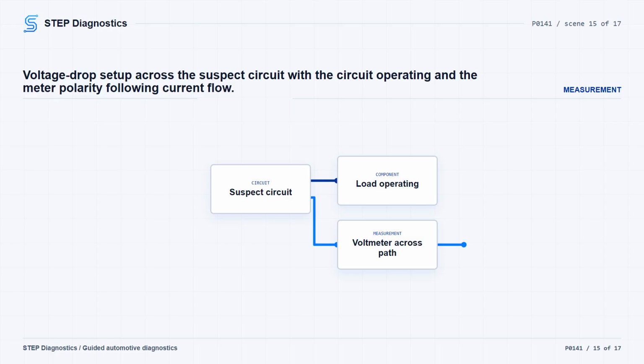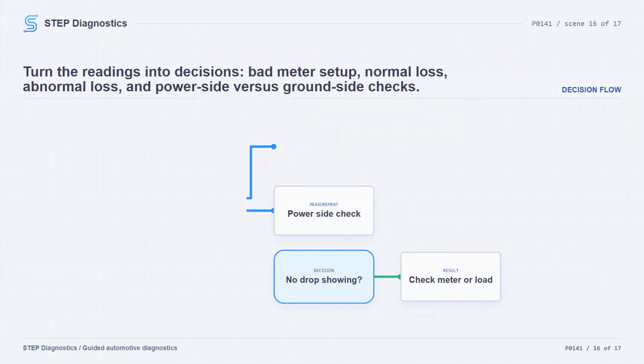For voltage drop testing, connect the voltmeter at the beginning and end of the suspect circuit, with the circuit operating or trying to operate, and power available. Connect the meter lead so polarity follows conventional current flow. A 0-volt voltage drop reading usually means bad meter connections or the component has not been turned on. A small amount of voltage is normal circuit loss. In 12-volt circuits, normal loss is usually less than 0.5 volts, or less than 5% of circuit operating voltage. Greater than 0.5 volts indicates abnormal voltage loss from high resistance in wires or connectors.